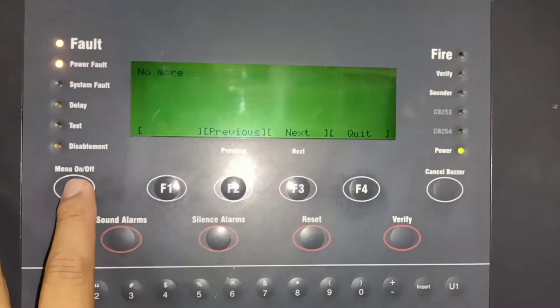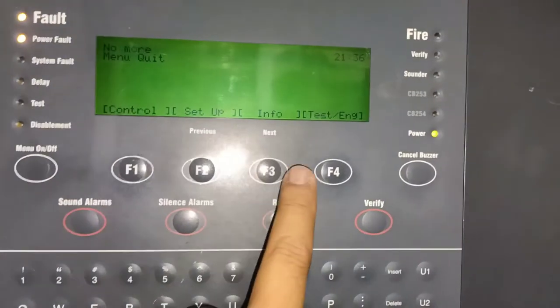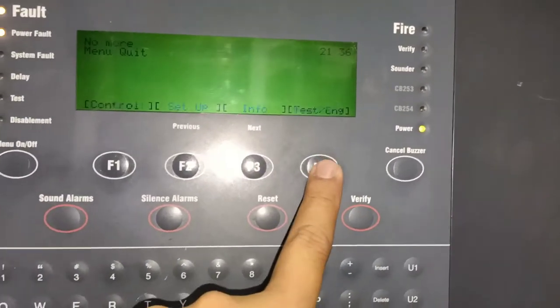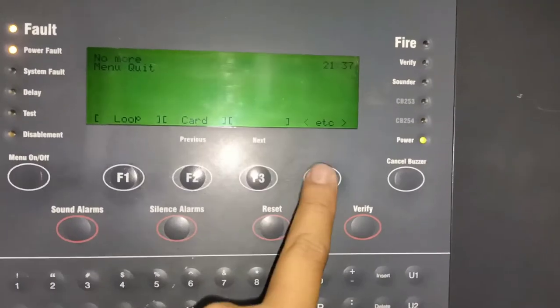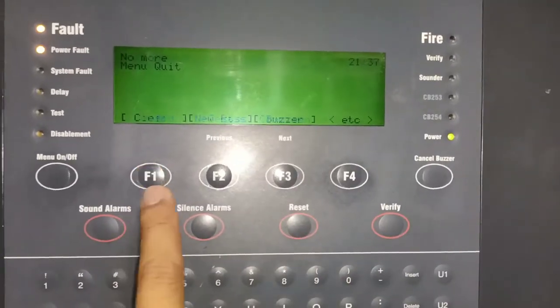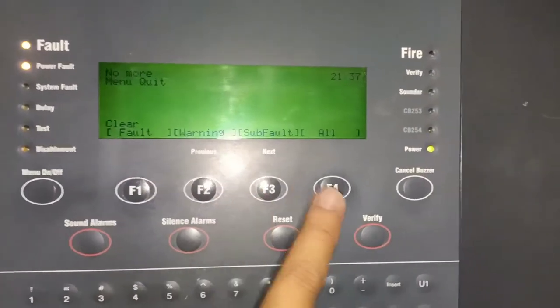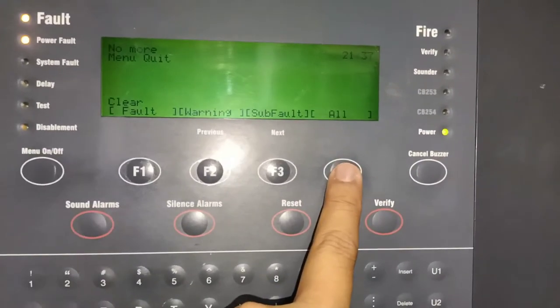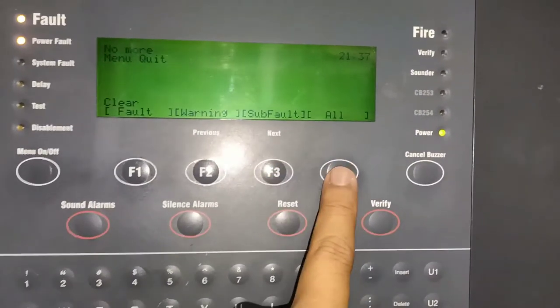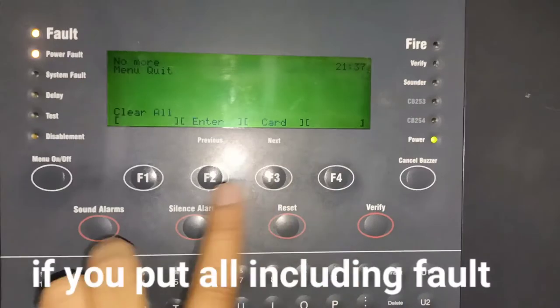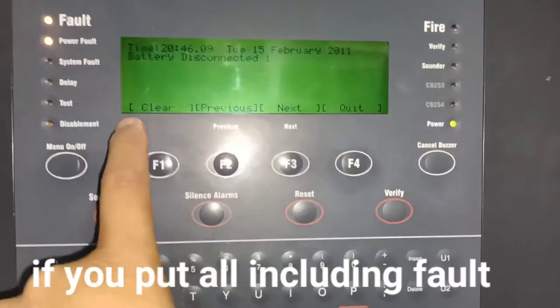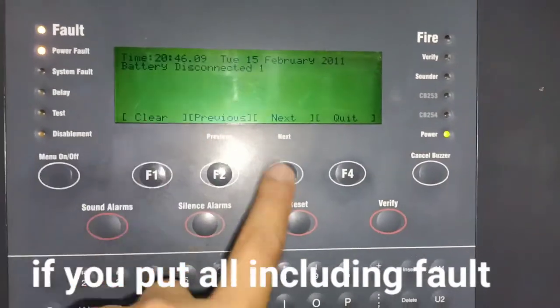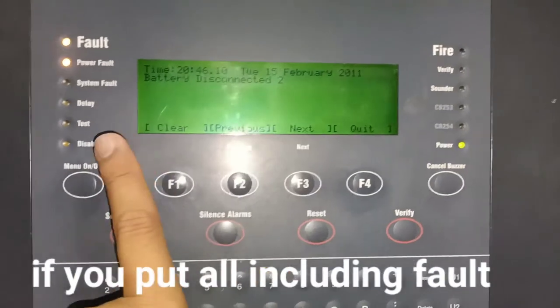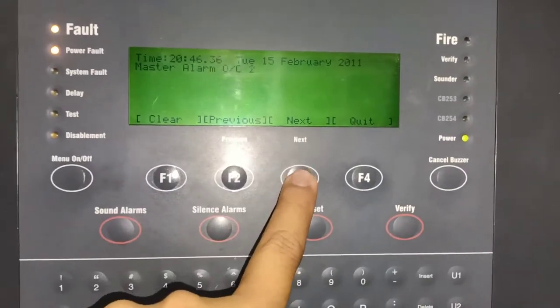Okay, I will repeat. You can go to this engine, then config, clear, or you can put subfault, or you can put all. If you put all, you can see the troubles also. Battery, this one is battery, has a battery trouble, disconnected because it didn't have a battery, and an open circuit for this one.